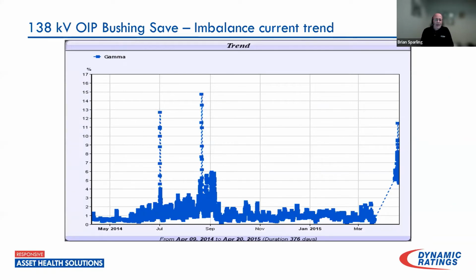So when we're looking at saving bushings, the trend of the imbalance current is all important. It does change over time. It can change because of temperature change if it's defective, or voltage change, a slight voltage change on the bushings of the transformer, applied voltage on the transformer. But the point is, once it begins to increase, there's no going back. It has to be replaced.